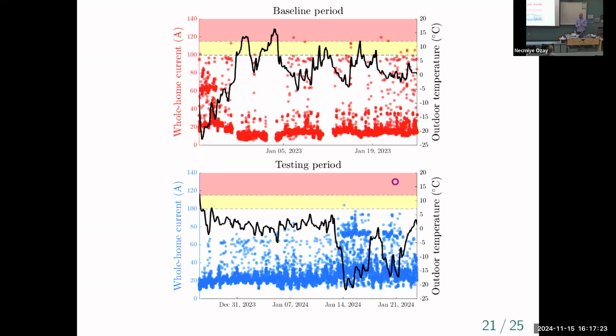And I think this is not a huge issue because it turns out, if you look into the details of what makes circuit breaker panels trip, there are two mechanisms. One is a magnetic tripping, and there it looks at really fast time scale, fractions of a second type currents. So a sudden surge for a microsecond can trigger a magnetic trip. But usually those only happen when you're several times higher than the rated limit. So if your limit is 100 amps, it might trip if you're at 200 or 300 or 400 amps. So we're at no risk of magnetic tripping here, but there is a thermal tripping mechanism where basically a piece of metal gets too hot and then it trips a switch in that way.